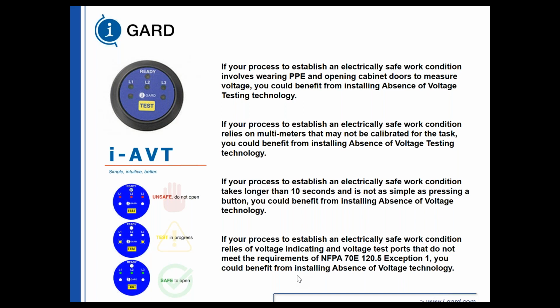But we've cut down establishing a safe workplace to 10 seconds. And up until this point, you haven't had to wear any PPE, and you can do all this with the door closed. So before you put on any PPE, you can actually verify that the voltage is absent with UL 1436 and SIL3 and the i-Gard i-AVT. So installing the i-Gard i-AVT will cut your process of establishing a safe workplace by 20 minutes. But more importantly, it helps you save lives because, as we saw earlier, most people get hurt or injured, killed, establishing a workplace safe condition. And so we'll eliminate that hazard.